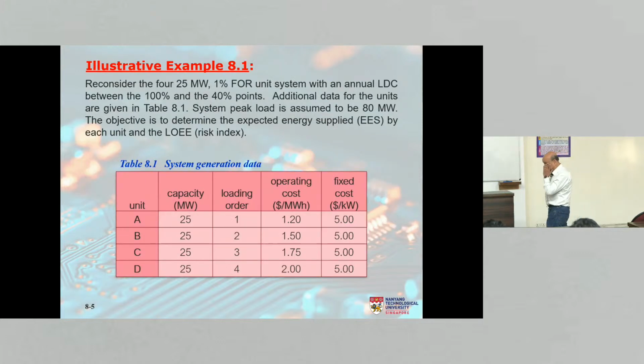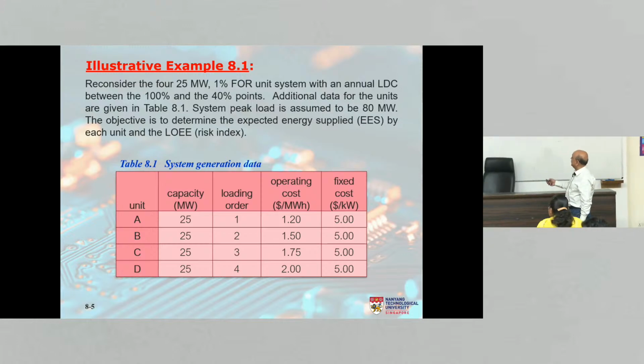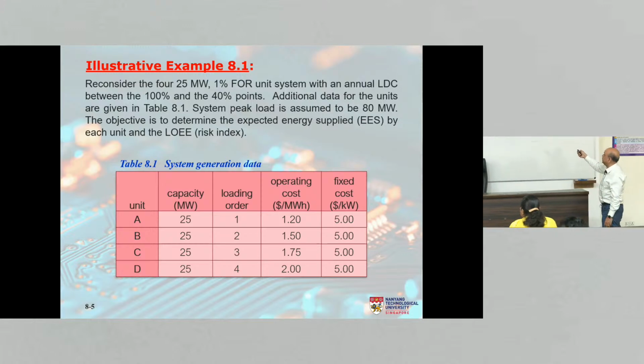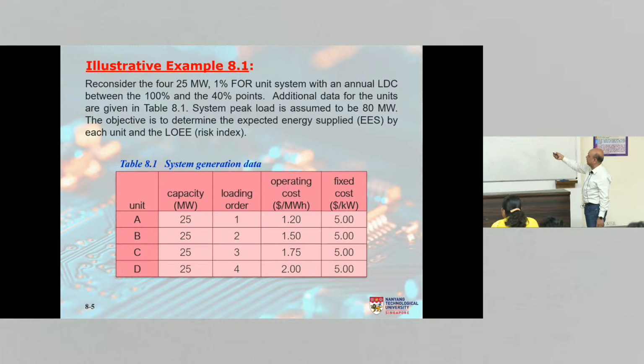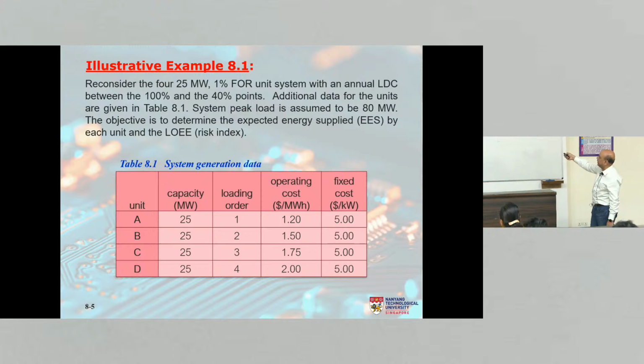So we go to our example, the famous way of learning, and we go back to our same system: four 25-megawatt, 1% unavailability generating units with an annual load duration curve between the 100% and the 40% points. The system peak load is assumed to be 80. So 80 represents the 100% point, and 80 times 0.4, 32 megawatt, will be the lowest load point. It is a straight line, so that makes our calculations easier. The objective is to determine the EE, energy supplied by each generator, and the risk, loss of energy expectation.